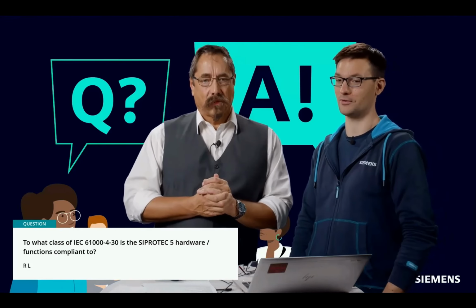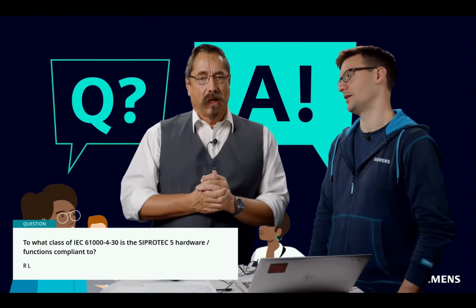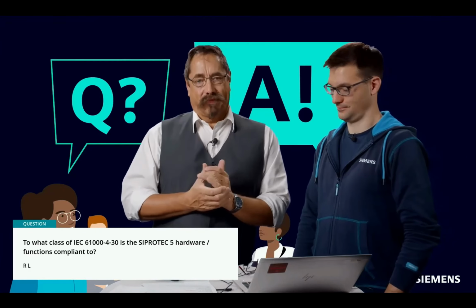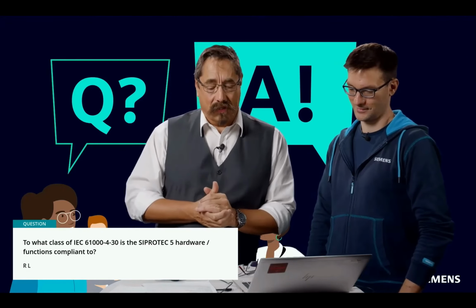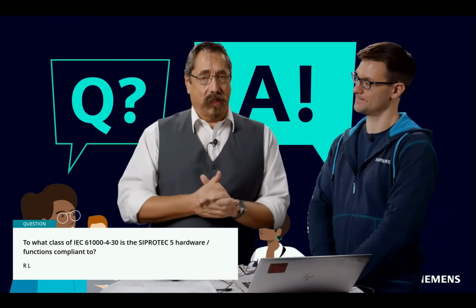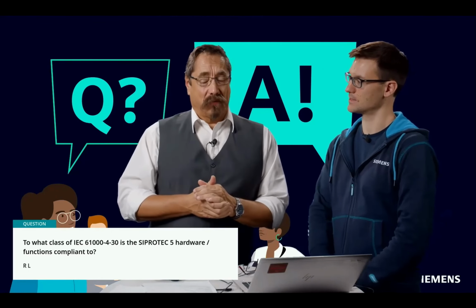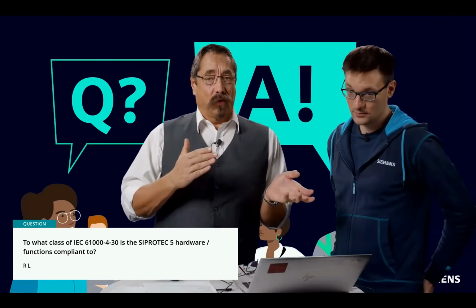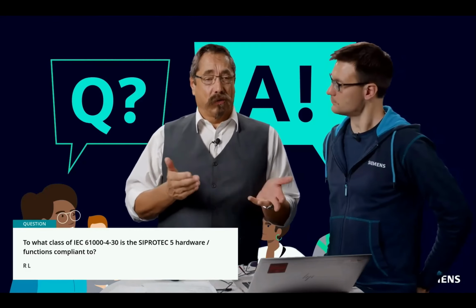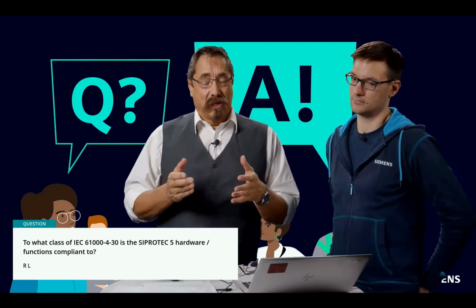We have a question regarding power quality. What class of IEC 61000-4-30 is the SIPROTEC 5 hardware functions compliant to? Yeah, it's class S. It's not class A. Class A is an accuracy of 0.1%, but for that we have in our portfolio PQ recorders like the Q100 and Q200. These are class A machines.